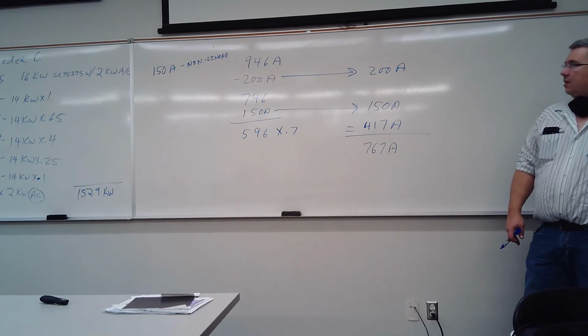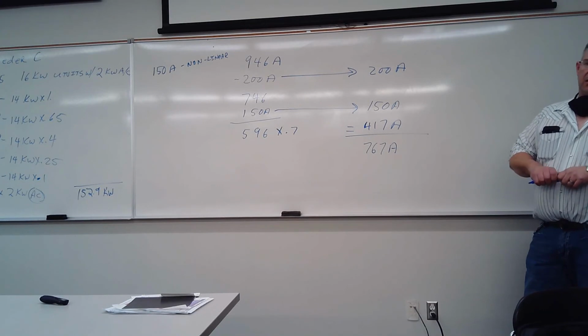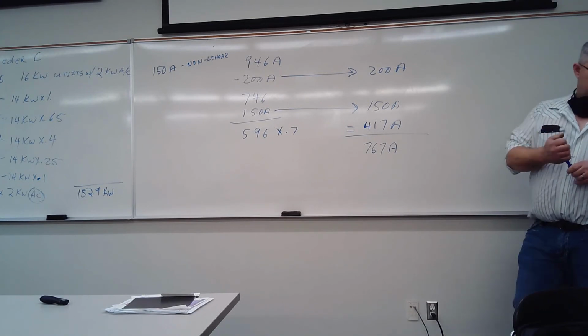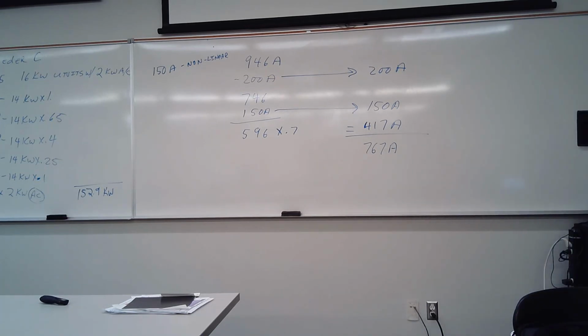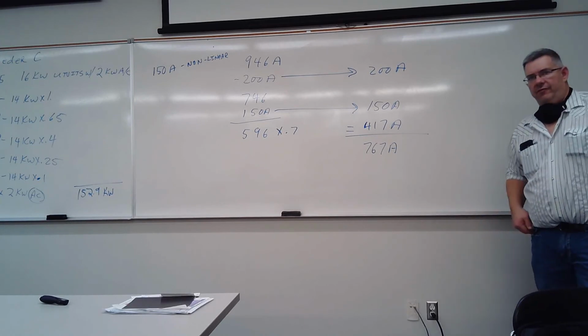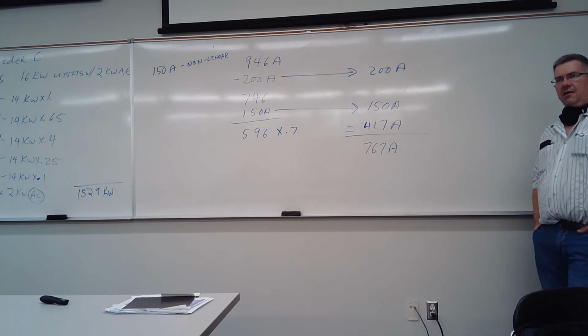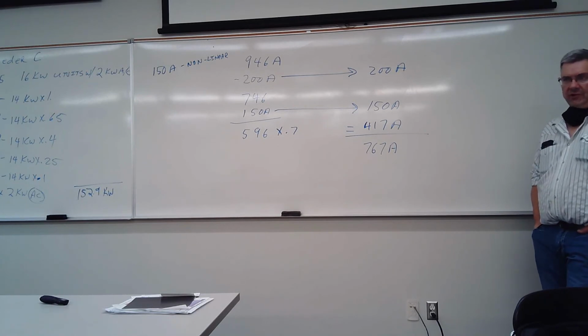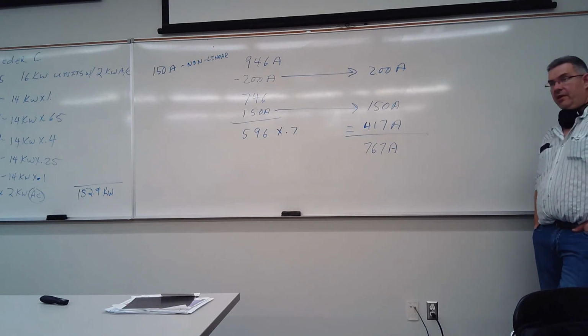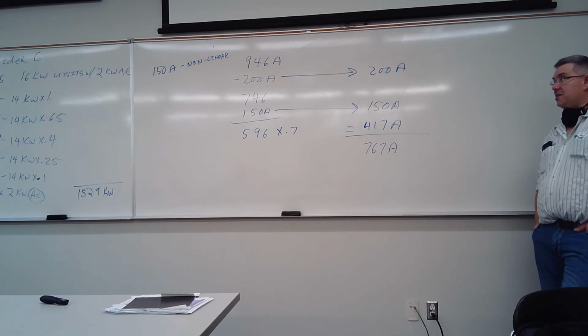Save a couple of bucks, eh? Yeah. Especially the long run, I guess. The conduit's a little less full. I mean, if you're pulling 80-foot long runs of 750 aluminum, I don't know what the cost of that is. Those conductors each are quite a bit of money, right? So if you can reduce by $300-400, good deal. If you're pulling 80 feet of conductor, I'd rather pull three 750s and one 400 kcmil than pull four 750s, right? I mean, it's just that much less weight to deal with and whatnot. It's going to make things easier, save a little bit of money.